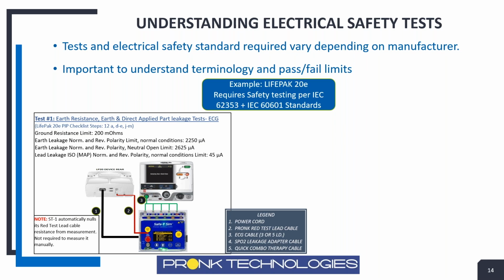And then you're doing what's called a leakage ISO, or what's referred to as mains on applied parts, where you're taking 120 volts AC and applying it to all of the leads on the device, and you're seeing what the leakage current going to ground is when you do that. And I'm sure you've done this test many times, where the analyzer will indicate, look, the leads are hot, and it really is applying AC voltage onto the leads. It's current limited, so it won't be lethal. But if you're feeling drowsy, it'll really wake you up in the morning if you happen to touch those leads, for those of you who've done it. And so you have to make sure you follow this according to that standard.